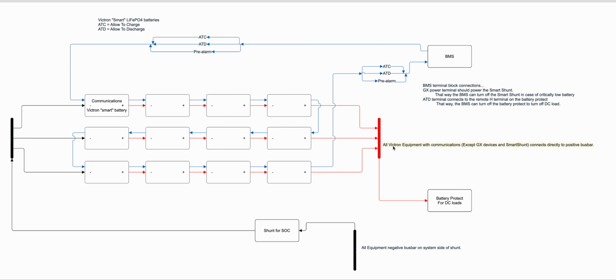One of the things I like about this scheme is the inverter is constantly connected to the battery no matter what. And so if the inverter receives a command that it's no longer allowed to discharge, then it turns off, but it turns off into charge only mode. So it's not drawing any power from the battery, but then if you start a generator or something like that, connect it to the grid, plug in shore power, what have you, then the inverter will power up off of the power supply on that AC input, and then it'll see that it's not allowed to discharge, but it is allowed to charge. And so then it'll utilize that AC source to start charging and power up the system.